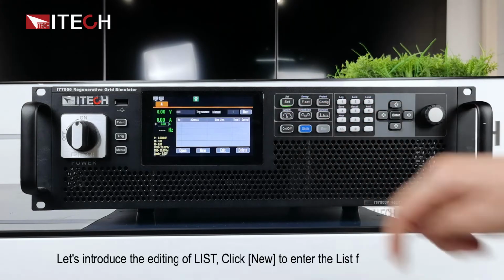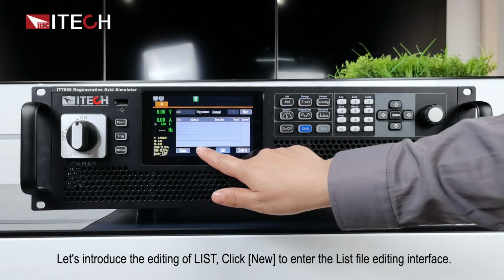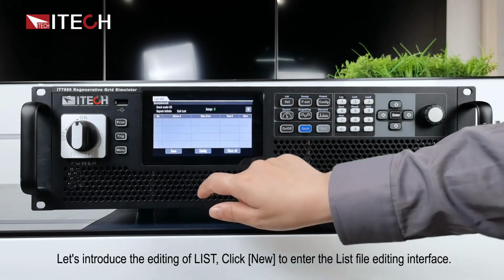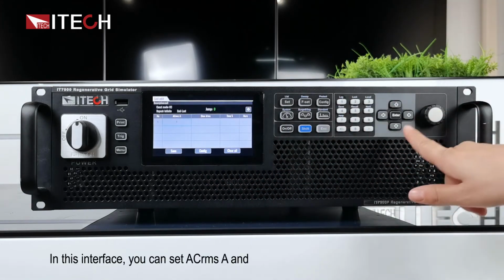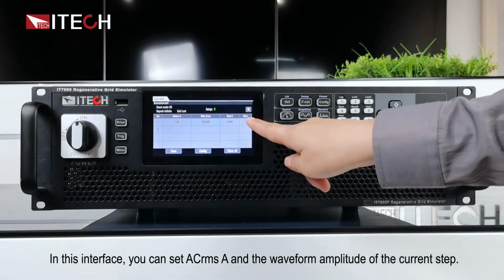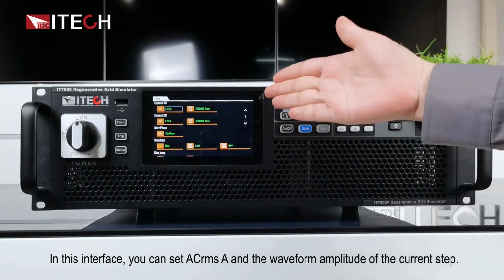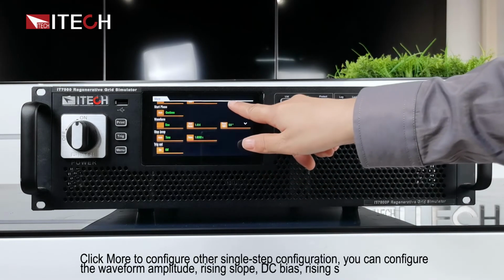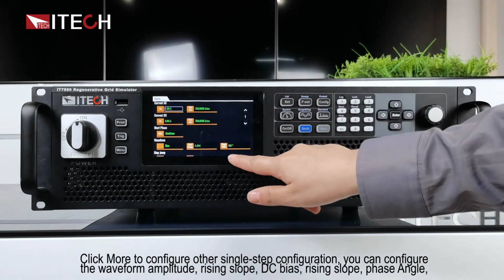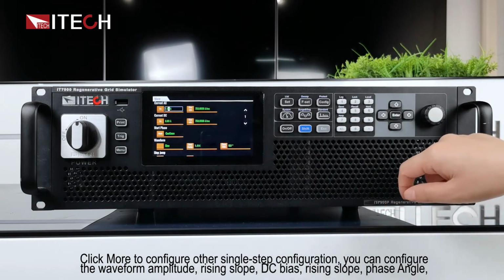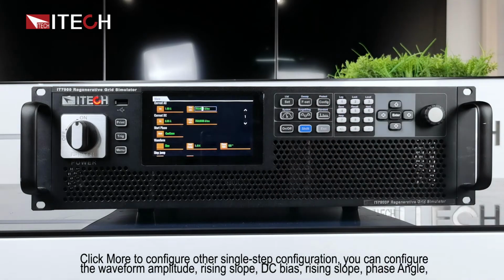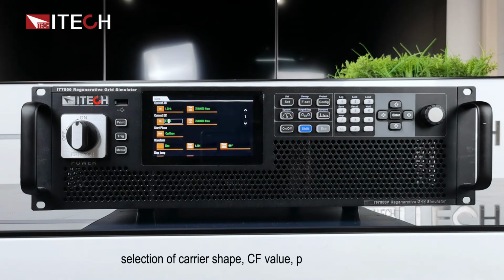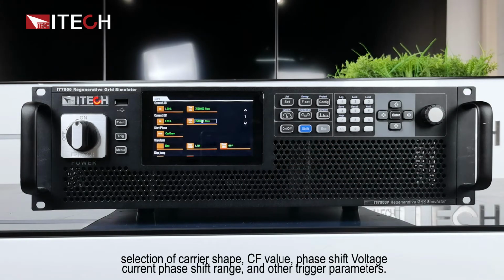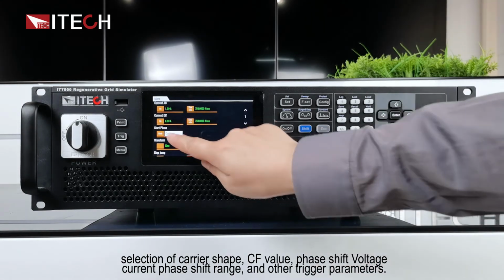Let's introduce the editing of list. Click New to enter the list file editing interface. In this interface, you can set ACRMS and the waveform amplitude of the current step. Click More to configure other single-step configuration. You can configure the waveform amplitude, rising slope, DC bias, phase angle, selection of carrier shape, CF value, phase shift voltage, current phase shift range, and other trigger parameters.